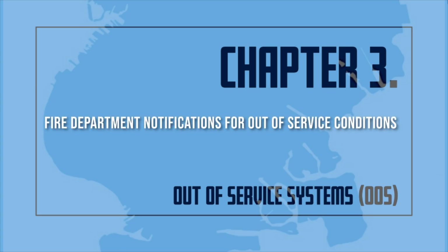Fire department notifications for out-of-service conditions. Notification to the fire department shall be made when a standpipe system is out of service for any period of time. The initial fire department notification shall include the following. 1. The owner or impairment coordinator's name and contact information. 2. The building address. 3. The type of fire protection system that is out of service. 4. Whether the fire protection system is out of service by reason of a planned removal from service, and if so, the reason for placing it out of service, or of an unplanned out-of-service condition.